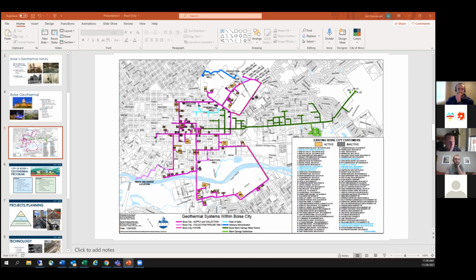The whole time, they're getting charged for every gallon crossing their meter. So we put a crossover at the end of that service, again just bleeding a little water, kind of like the analogy of a shower where you turn it on and don't want to wait too long for hot water to start coming. Once we put that crossover in, immediately every time this building calls for heat, the hot water is there for them. That solution solved the issue, and we've replicated it in multiple places across our system just to keep water moving so nothing sits stagnant.